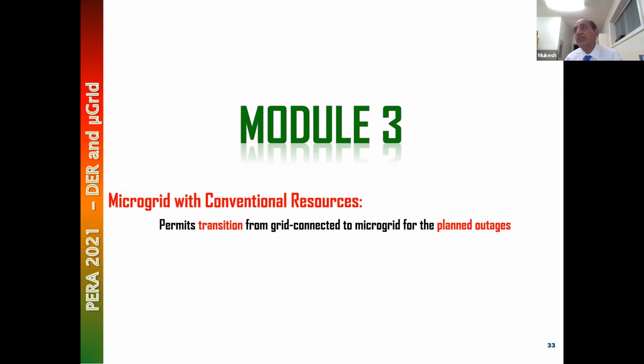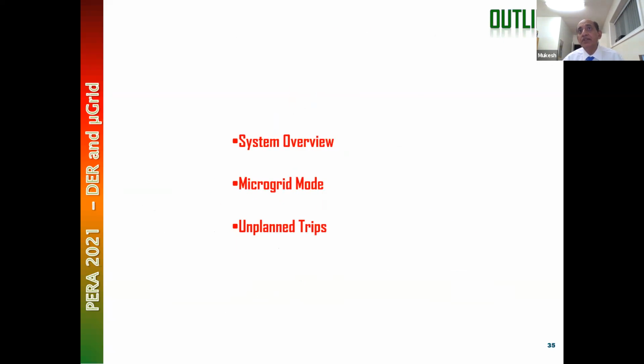The microgrid operation is a planned operation, meaning in the previous case, when the fault happened, the switch from grid to microgrid happened automatically. In this case, switching from grid-connected to microgrid, or microgrid back, required certain manual operations because we did not put enough communication infrastructure to allow automatic transfer. So I'll talk about some of them. I'll talk about three things: the system, then what we did to make it work as a microgrid, and then, in spite of doing all the good things, we still had, in microgrid operation, at least two occasions of unplanned trips. I'll share those with you.